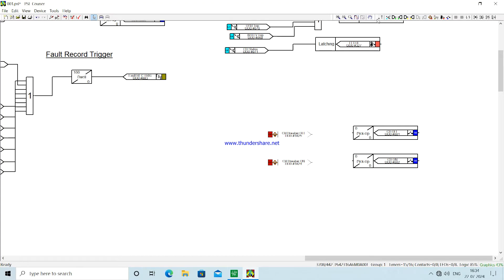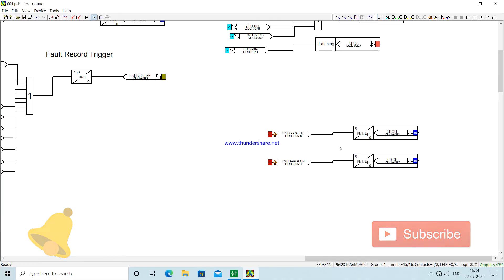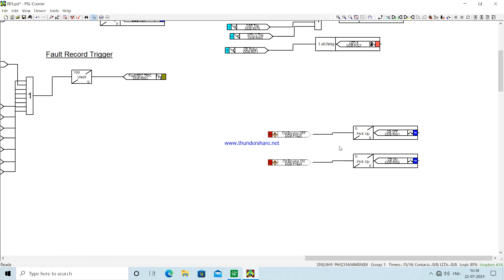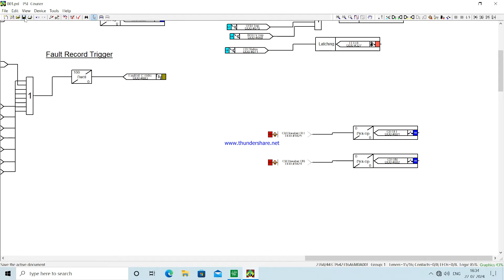We will simply connect control input one to CB on and control input two to CB off. To show the circuit breaker CB status, it should be given through an opto input as already configured in the PSL — you can see in LED number eight for CB status.